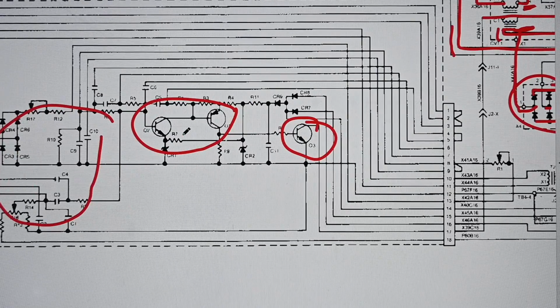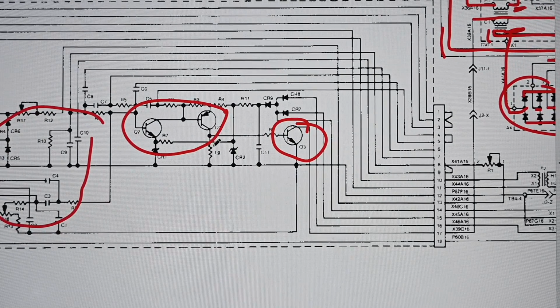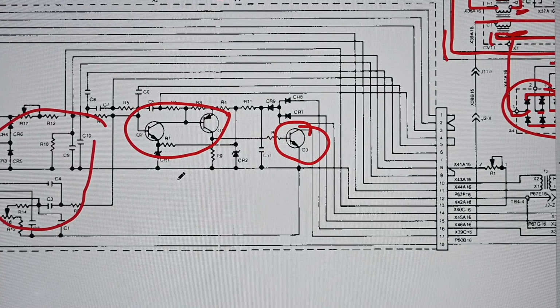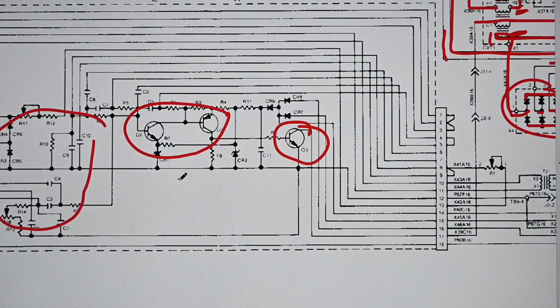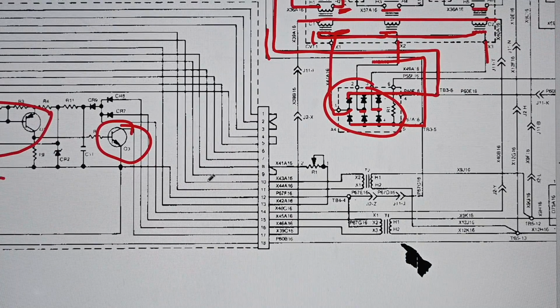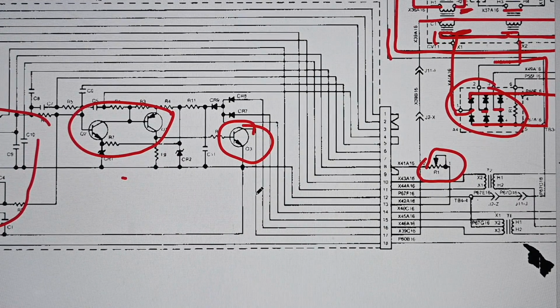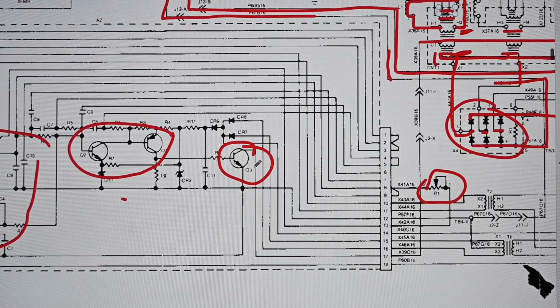This voltage regulator is essentially looking at a constant reference voltage, set by R1, the voltage adjust rheostat, which has the set point. If the main output of the generator set varies above or below that reference point, this transistor is driven further or less, as needed, changing the main output voltage and bringing it back in alignment with the reference voltage within the regulator.